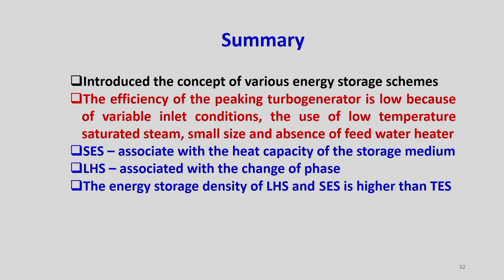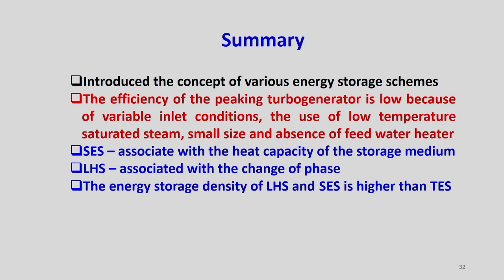So we can summarize what we have discussed today. We have introduced the concept of various energy storage schemes. Primarily in this lecture, we have discussed thermal energy storage systems, which include sensible energy storage, latent heat energy storage systems, and thermochemical energy storage systems. And also, it is found that the efficiency of the peaking turbogenerator is low because of variable inlet conditions in case of thermal energy storage systems, and the use of low temperature saturated steam, small size and absence of feed water heaters.